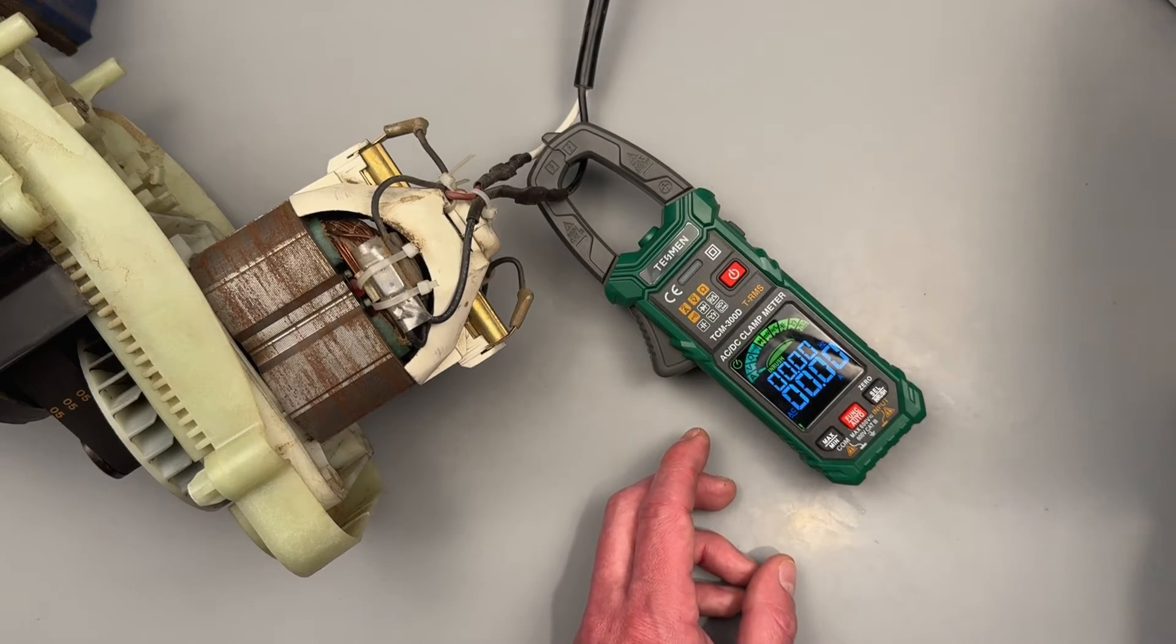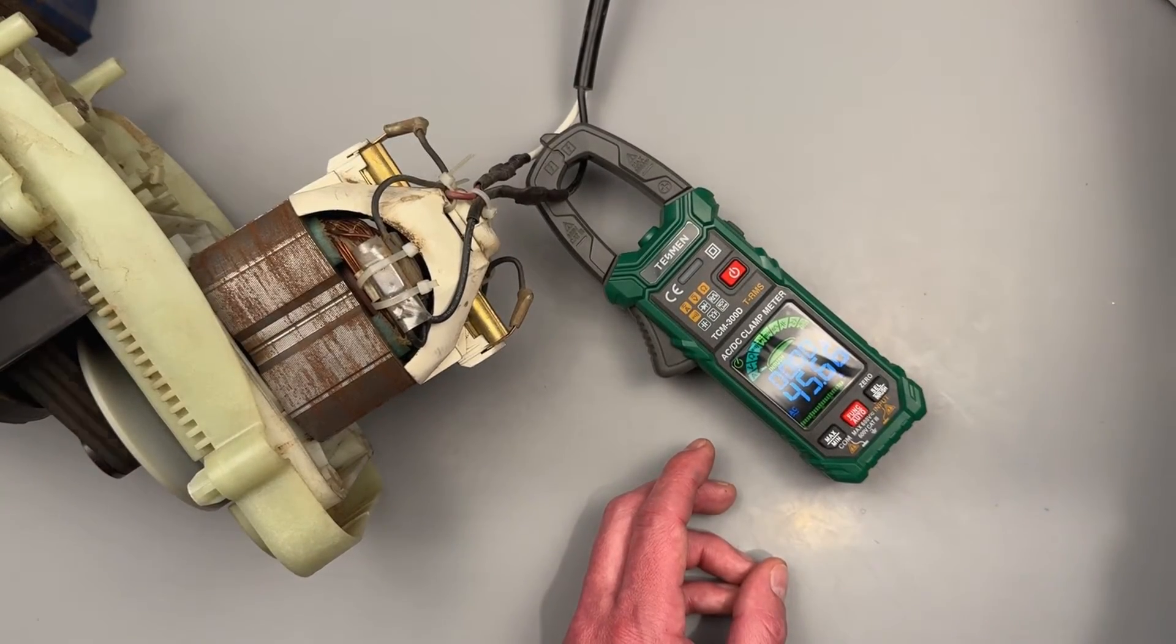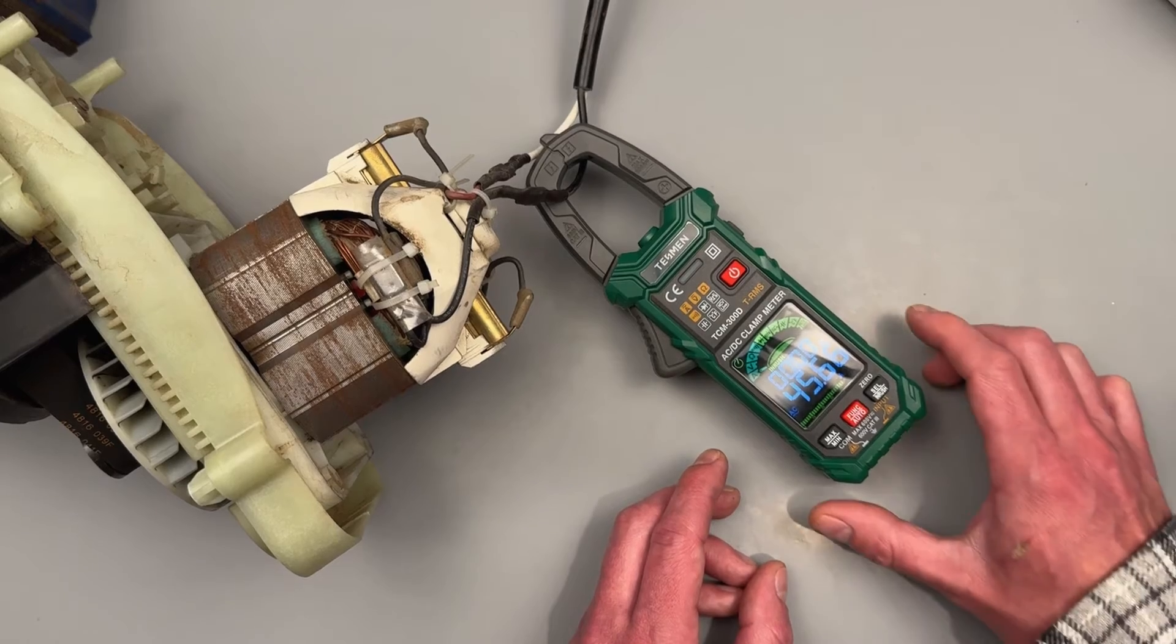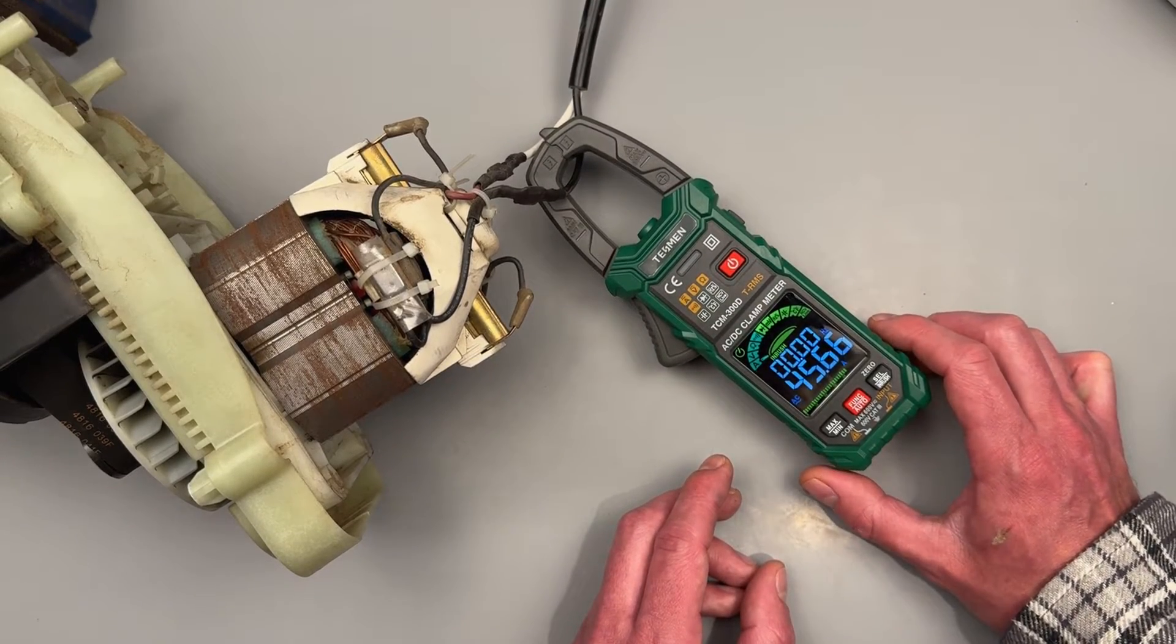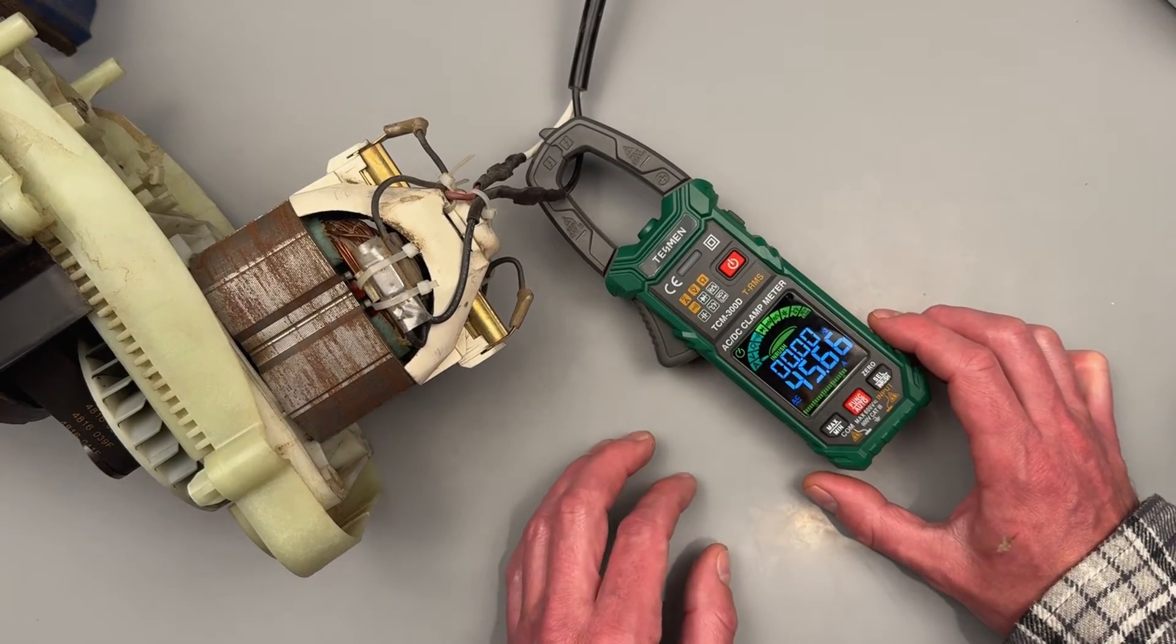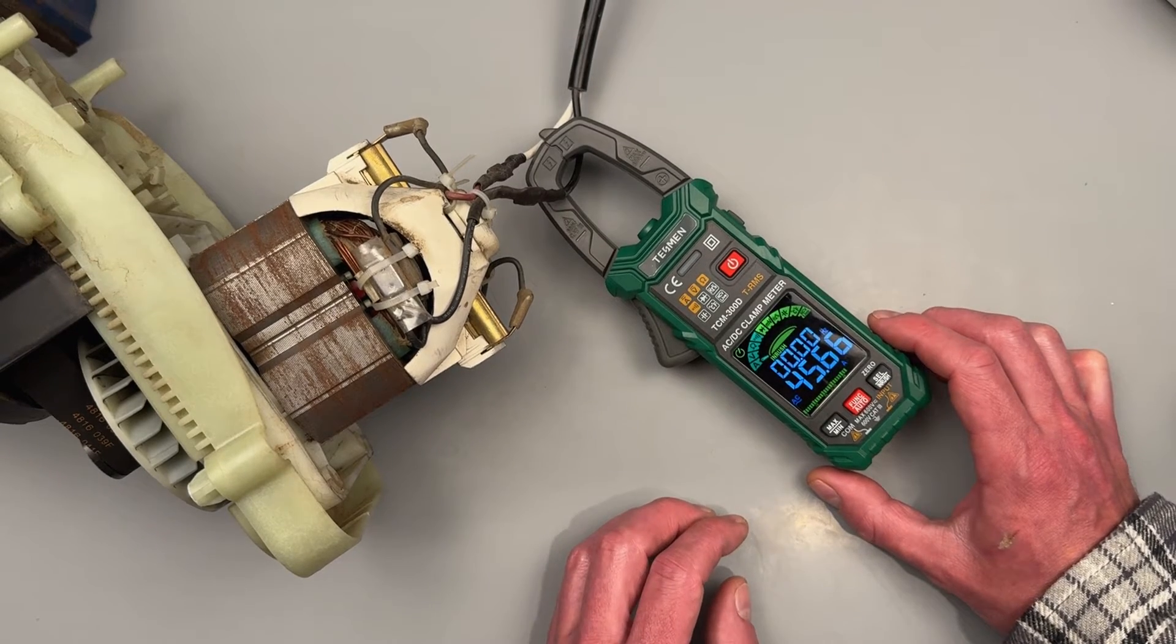I'll flick on this motor really quick and let's see the number that it comes up with. Okay, so this is telling us it took about 45 to 46 amps to kick on this motor initially. That's a pretty cool function.